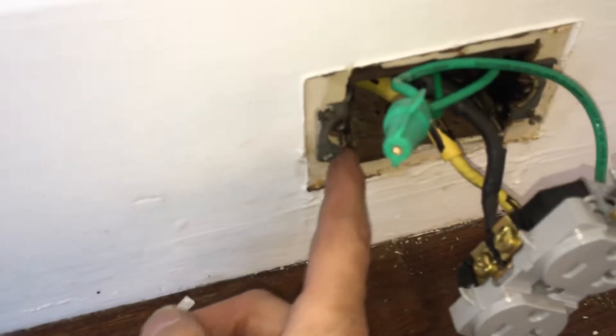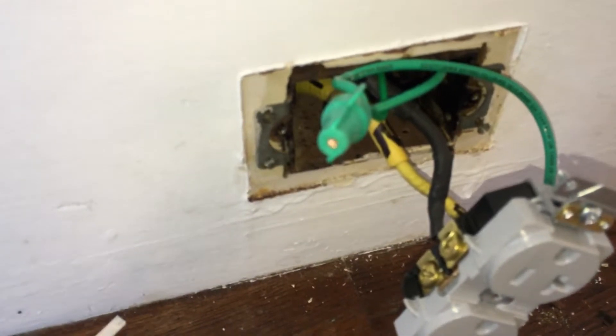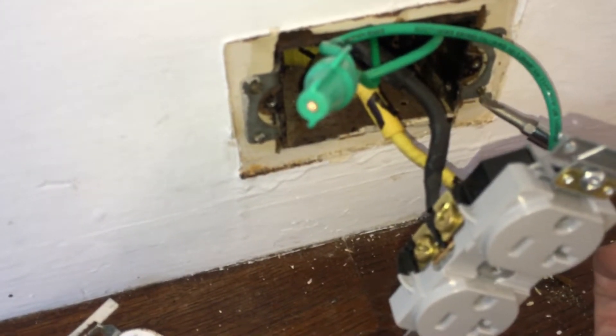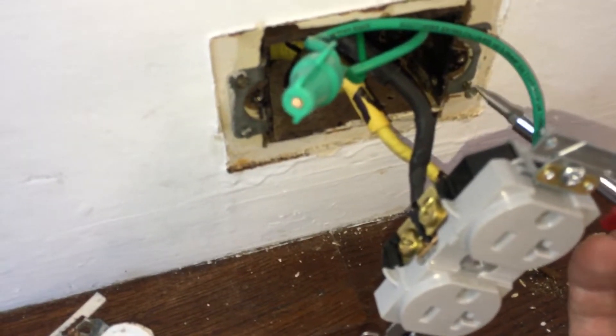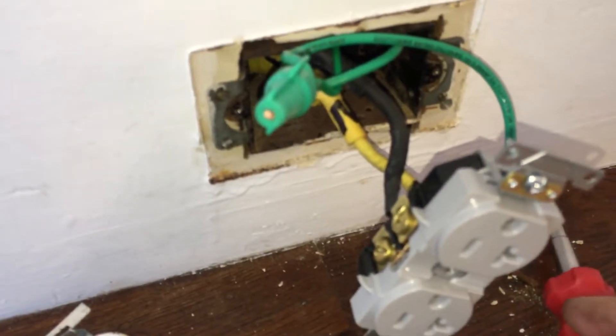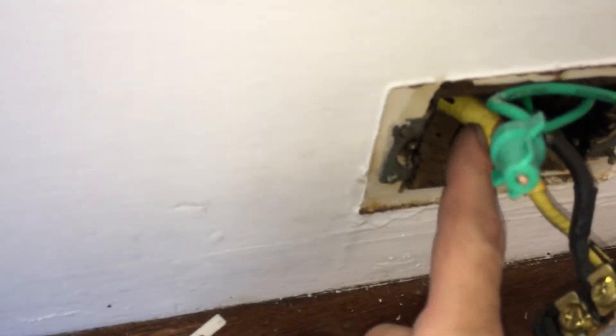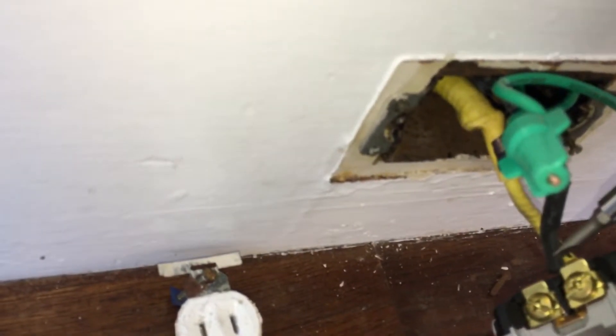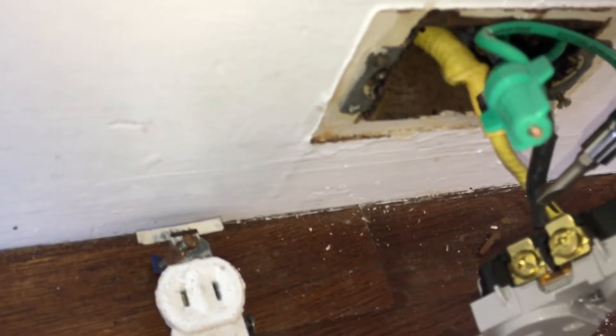Old metal box like this. You can tell how old they are - on this one right here it has brass screws with a single slotted thread, and they're made out of brass. That puts you decades earlier. The old material cloth winding was decaying and falling off - it was very brittle. The actual rubber that was over the copper wires was deteriorated.